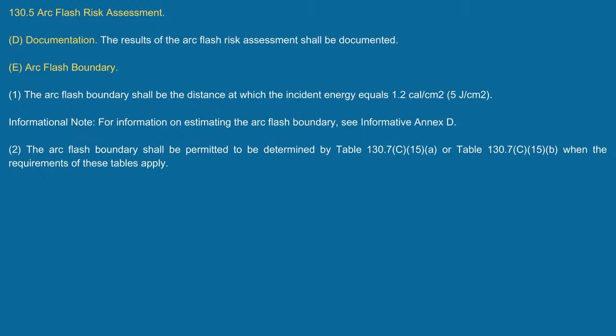Now, looky here. Also, the arc flash boundary shall be permitted to be determined by what? Table 130.7(C)(15)(A) or (B). All right? It's already given to you in there if you meet all the parameters and everything that's in that table. Okay? Hey, didn't we come up with something from Mike Barr on that 1.2 cal thing where they just round up to like 2 cal, or wasn't there something controversial?